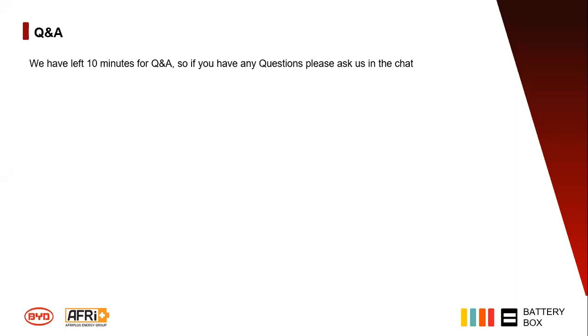We've got a guide, minimum recommended batteries, and it always shows the amount of batteries you should put with which inverter. If you follow that guide, then the batteries fall under the warranty. If the batteries are installed outside of those parameters, where they're not installed with the minimum recommended, then unfortunately they're outside of the battery warranty. The battery itself has a safety feature on the PC board or the BMS to protect the cells. That's when the tripping will happen most of the time, or there will be a warning signal on the LED lights, which on the new model shows the battery pack going into self-protect mode to protect itself. Usually I don't think you can continue using the system. It will force a shutdown.